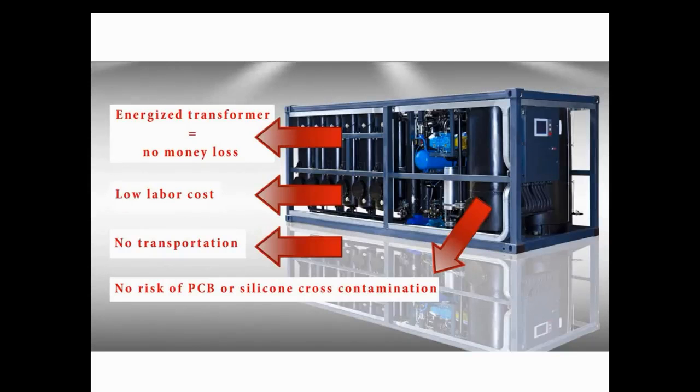Other advantages of regeneration are the following. When energized, the transformer means no money loss and no inconvenienced customer. Regeneration is easy to do by one operator. No oil transportation is engaged. Now you can see that regeneration is safer and more cost-effective than oil change.